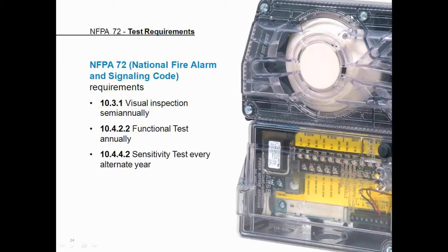Though this is what NFPA states with their testing requirements, at System Sensor, we recommend that different environments may require testing to be done more frequently. So we always suggest that NFPA testing should be a minimum testing requirement and do more as needed per the environment that the detector is installed in.